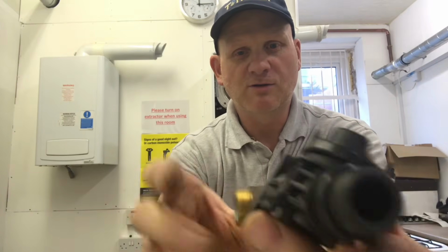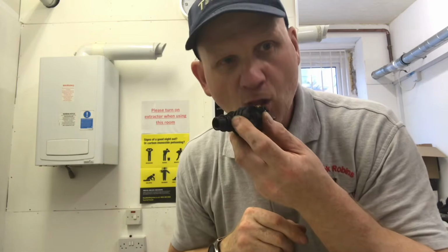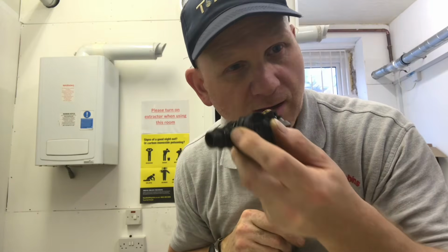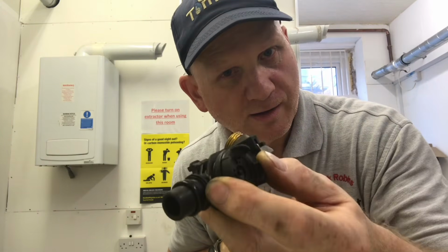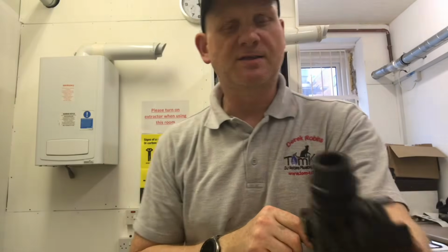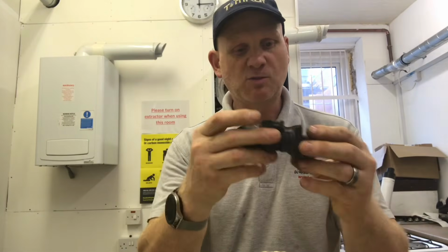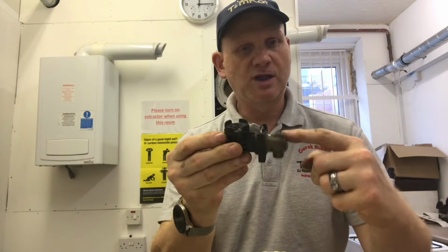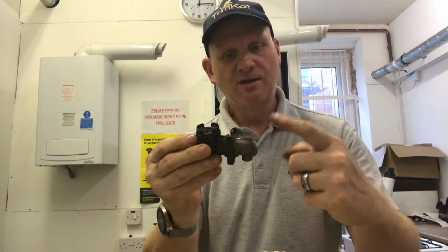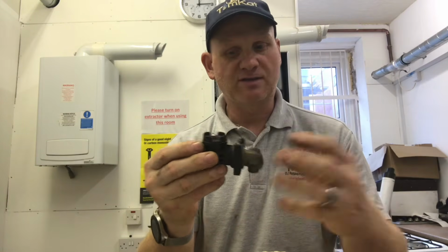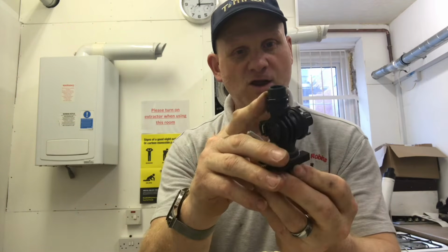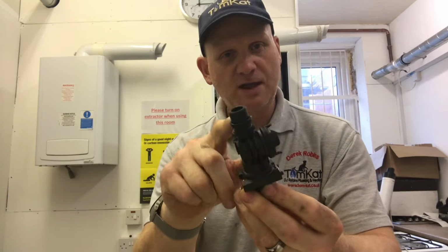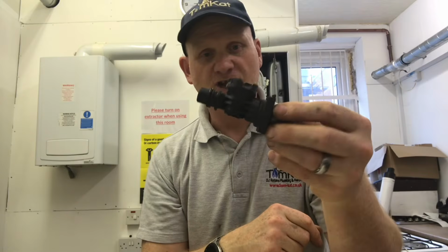Okay, this is where the water comes in and the water goes out. So if I blow through here, you can hear the turbine spinning inside. Okay, now this is a complete unit. This clamp is only holding this brass section on here, so if I undid the clamp, this brass section would come off. Now again, this is an O-ring, so I'm just going to lube the O-ring up and put it back in position. This is just a standalone change unit.